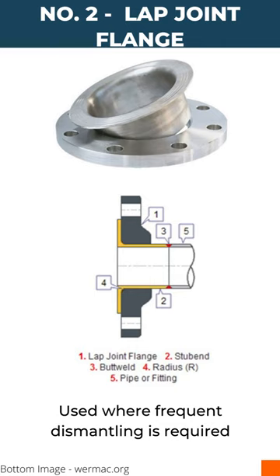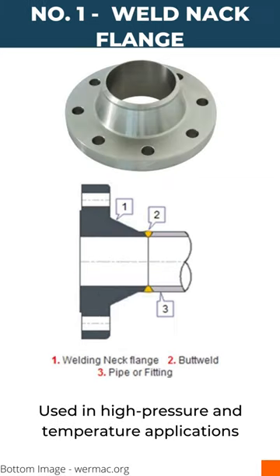Number two is the lap joint flange. The lap flange has two components: a stub end and a loose backing flange. It is used where frequent dismantling is required. The most used flange is the weld neck flange — number one — which is used in high pressure and temperature applications.